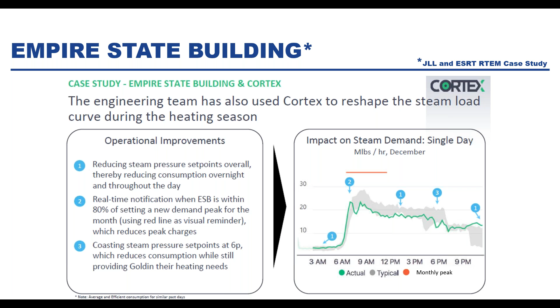They're doing the same thing on the steam system in this project. Steam is pervasive throughout New York City in large commercial buildings, especially in Manhattan, and it's a pretty outdated and inefficient system, so achieving steam savings is a big win on several levels, especially for emissions. Here's another set of operational improvements driving down the load curve, making sure not to set a new monthly peak, while still providing tenants completely adequate heating.